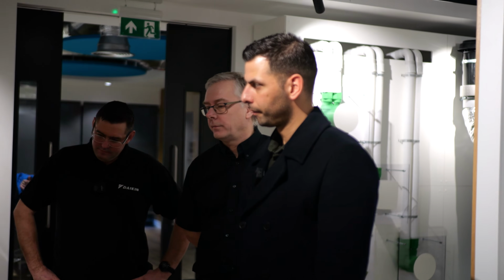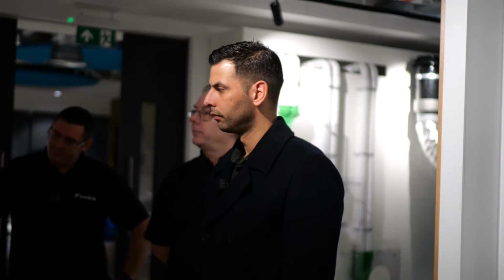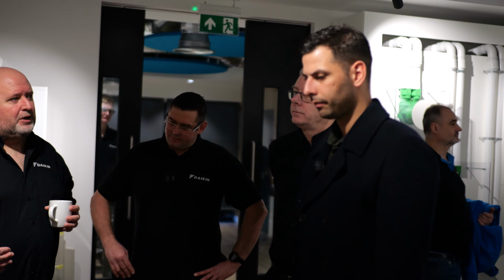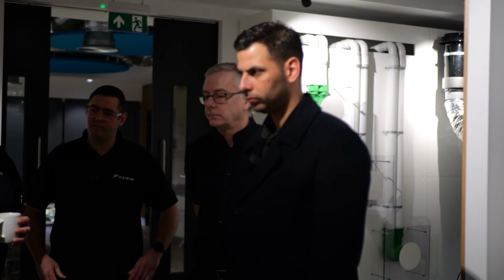I'm a big advocate of low temperature systems. We can talk later about insulating houses and stuff, because you don't necessarily need that insulation - at the end of the day it's just kilowatt in, kilowatt out. The problem is what size heat pump you'd need to hit a larger demanding property - that becomes more difficult.